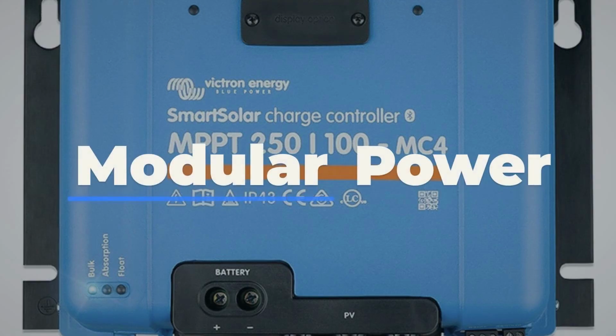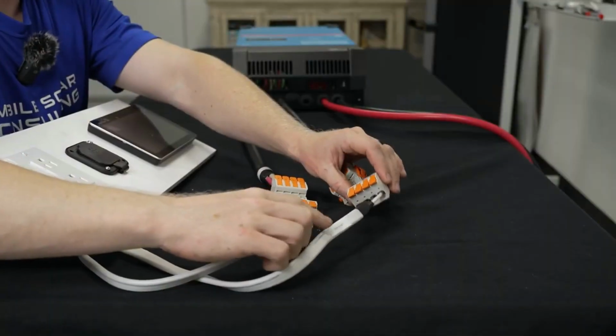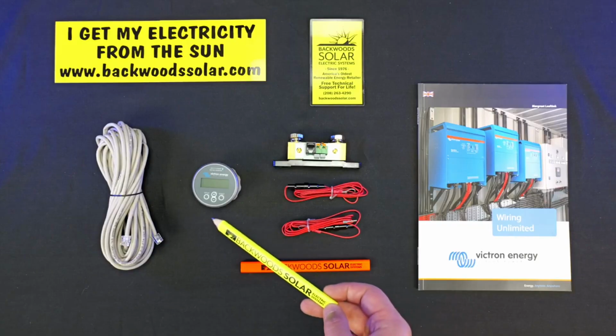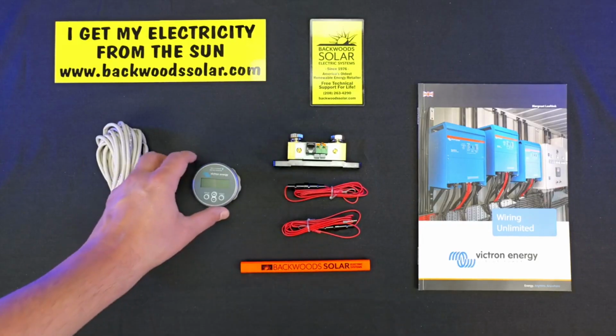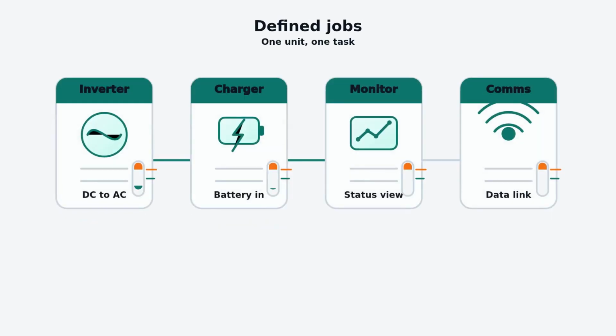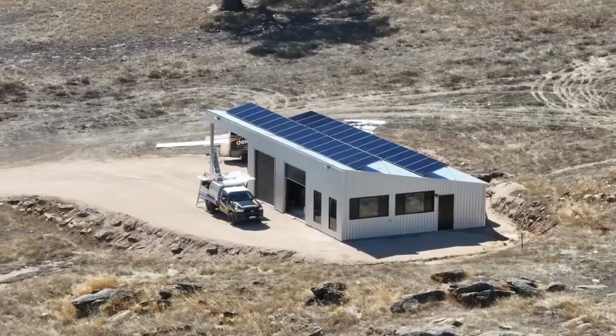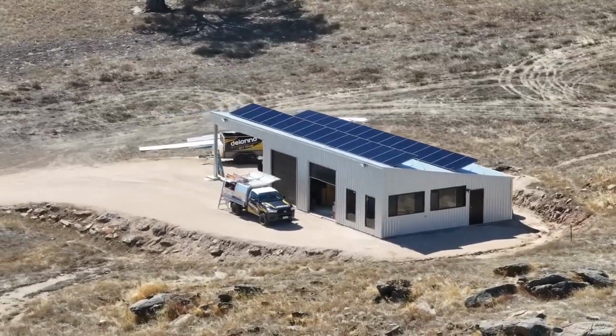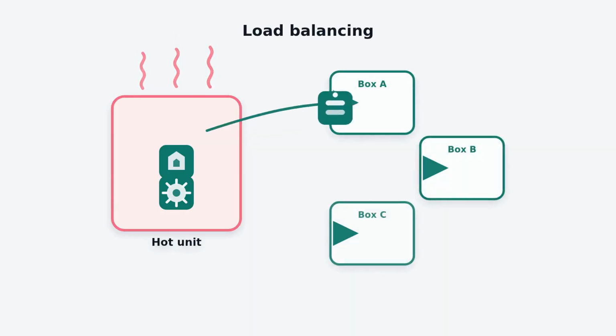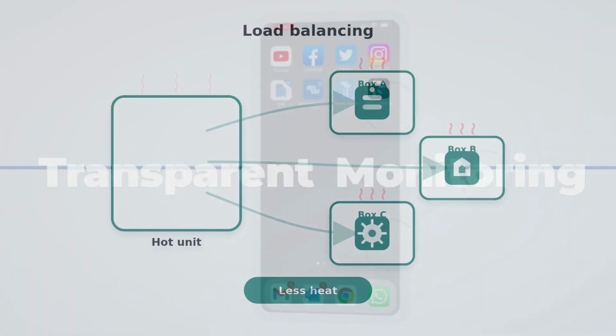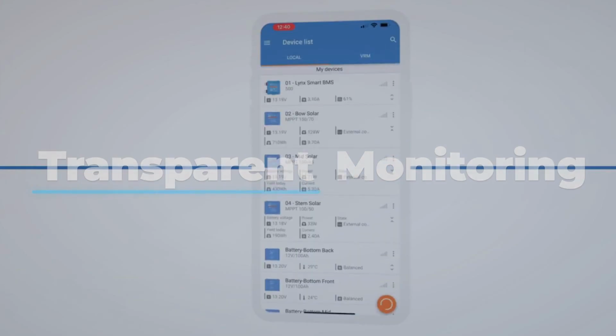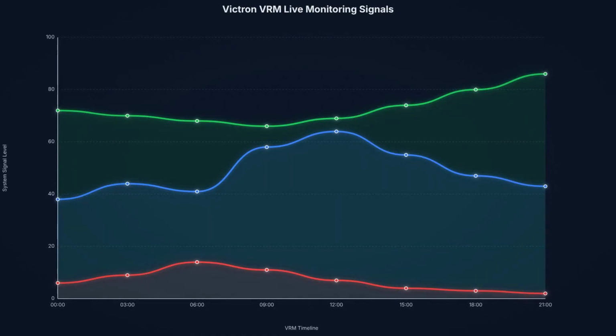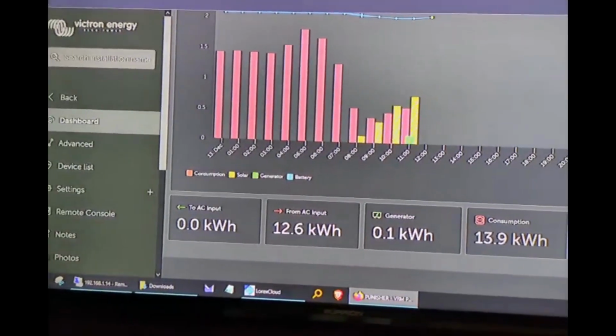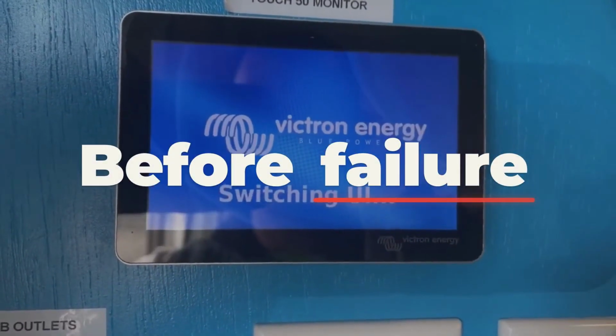Victron builds modular components. Separate inverter chargers, separate MPPT charge controllers, separate battery monitors, separate communication modules. Each unit handles one defined job with thermal headroom left over. That architecture means no single box is running at its thermal ceiling while simultaneously managing charging, inversion, and load balancing. You distribute the heat load by distributing the work. The monitoring is transparent in ways that matter. Victron's VRM portal gives you live data on every component, including state of charge trends, fault codes, temperature logs, and historical output curves. When something degrades, you see it before it becomes a failure.